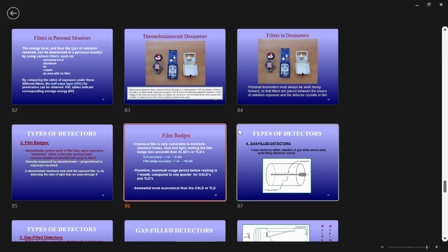So you guys, as radiographers, X-ray technicians, are monitored with either OSL badges, TLD badges, or film badges. All 3 are worn at the lapel level, outside of any lead aprons. The same thing will also be used as the fetal dose badge, worn underneath the lead apron in pregnant radiographers. Second badge worn down, usually at the waist level, behind any lead shielding.